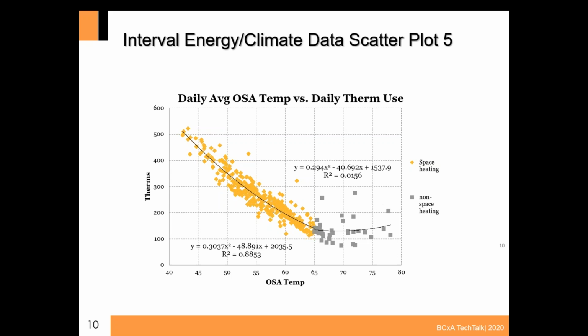Bethany asks, from the utility or the BAS, did you get hourly energy use from the utility or from the BAS? I work for a utility, and PG&E has installed smart meters across our facility at most buildings, so my tendency is to get it through the utility. But if it's trended, the power of the trend data is it might even be on a subset or a particular system, like the chilled water plant, and you can do the same analysis on subsets of your overall building energy use.